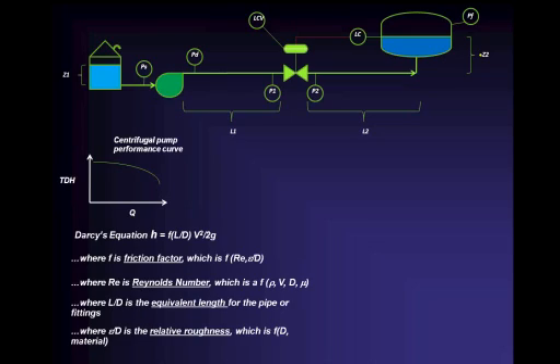I want you to notice something about Darcy's equation, the V squared term. In essence, we have an equation that, if you remember your analytical geometry, y equals mx plus b is the equation of a straight line. Well, this is not a straight line because it has a V squared term in it. This is a parabola, and you probably learned that in analytical geometry. So the friction loss in a piping system, H, the amount of pressure loss, is proportional to the square of the velocity.